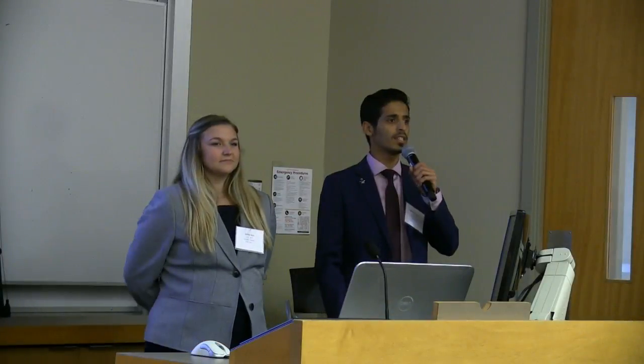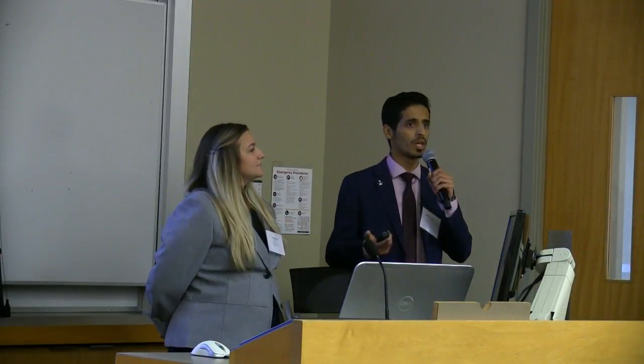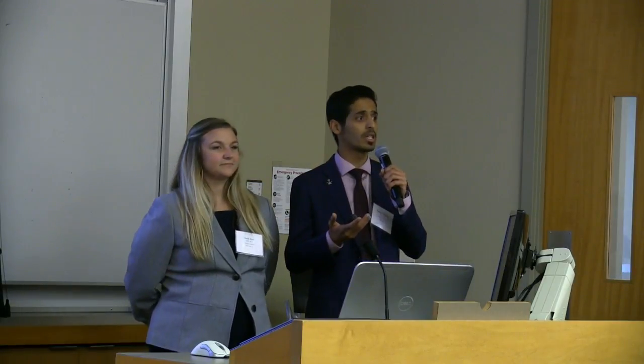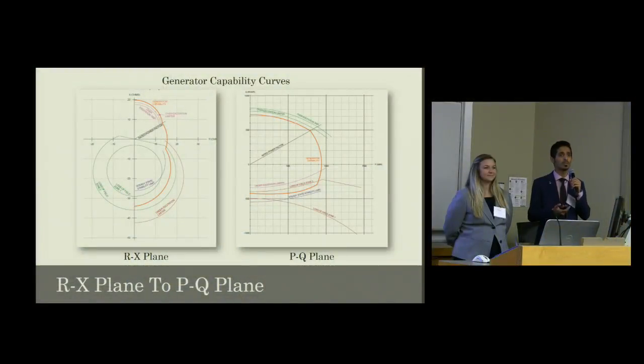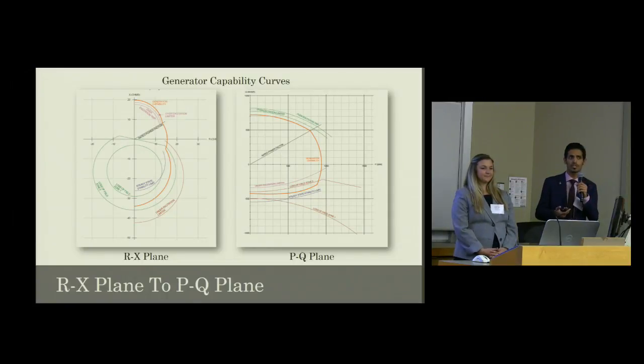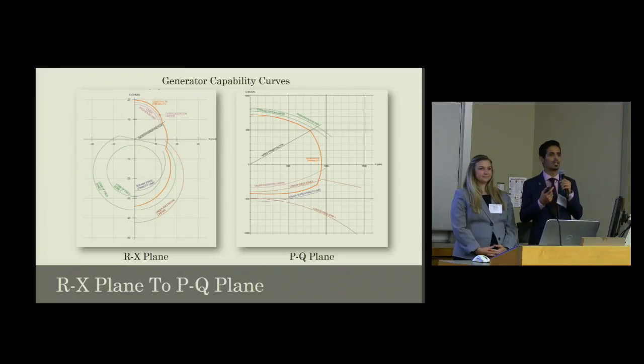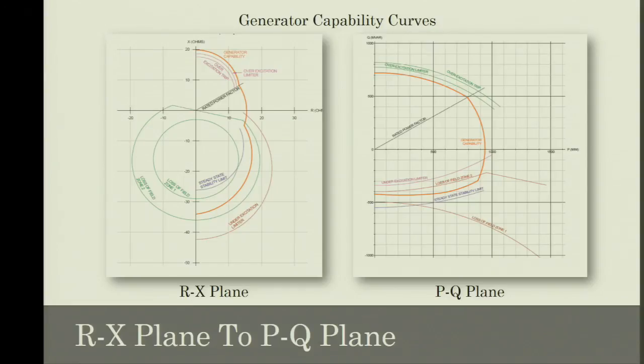So the GCCT is implemented in the PQ plane, which is the apparent power plane. However, some devices' characteristics are actually implemented in the RX plane, which is the impedance plane. For example, loss of field for the generator is implemented with distance relays, and those are activated based on the measure of impedance. If we look on the left, the two green circles are actually the two zones of the loss of field for a generator.